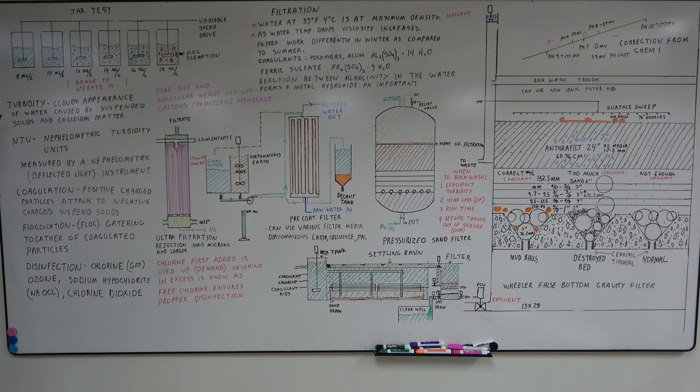Turbidity is the cloudy appearance of water caused by suspended solids and colloidal matter. This is what we're going to take out with the filtration. It's measured in NTUs, nephelometric turbidity units. It's measured by a nephelometric deflected light instrument. So you send a light beam down and then it measures the amount of light reflected from the particles.